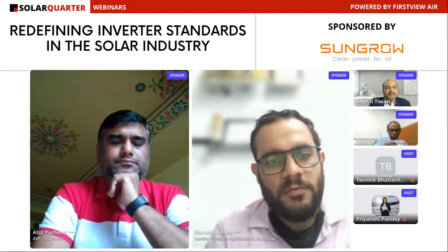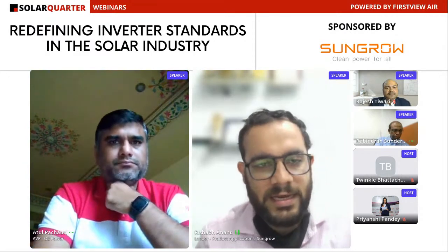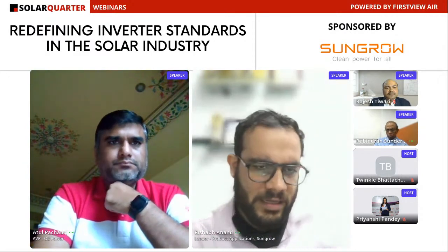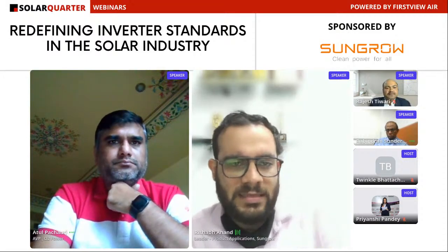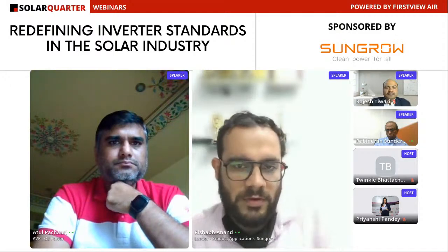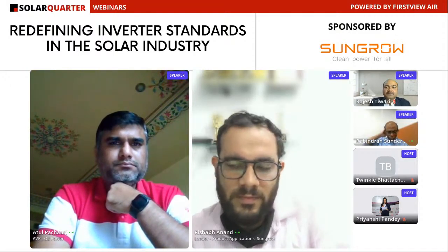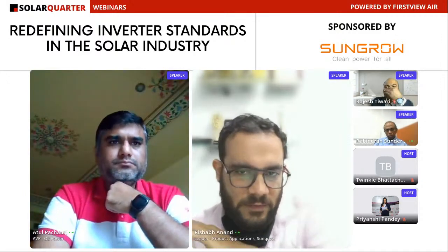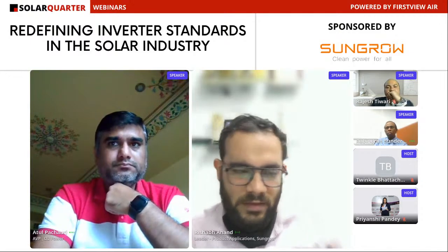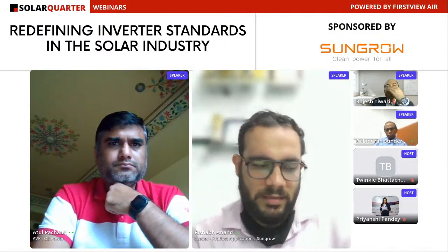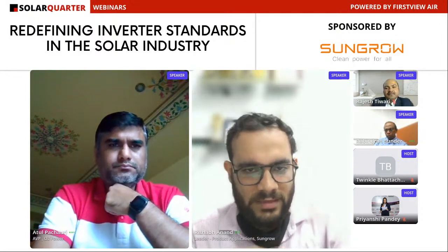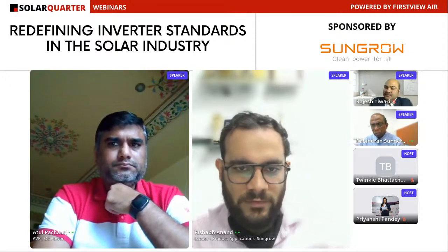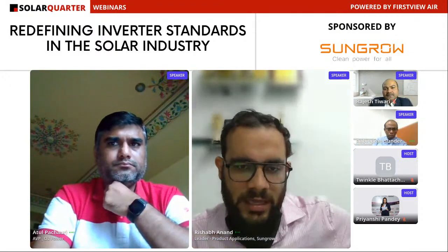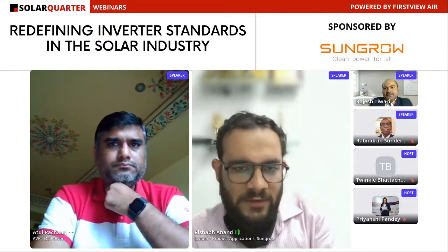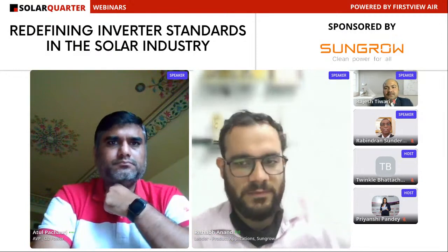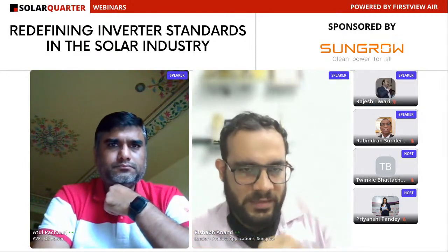SUNGROW has followed a two-part cooling philosophy for all outdoor inverters, wherein they segregate the high heat generating parts like the IGBT and the reactors from the very sensitive parts like the electronics, which are provided with closed loop cooling with heat sinks, while the IGBTs and reactors are provided with smart forced air cooling. What we have usually done is improvise on the cooling methodology and how the cooling path is followed. We have a distinct cooling path, a top-down or sideways approach, with a very short path between the air inlet and outlet, so the air is sucked down very fast and can evacuate heat at a fast pace because of the short path.